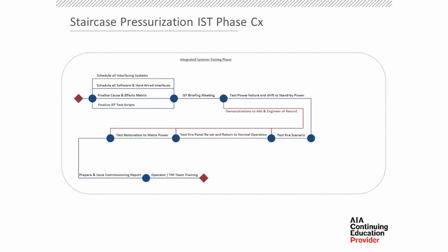So that's a mode you have to test it in. There's a series of tests you do, called out here: you start with a normal condition, then set the fire alarm off, then see the things come on, test it, then see it go back to normal power. All these sequences have to be tested.